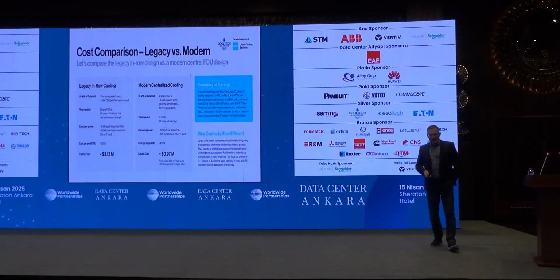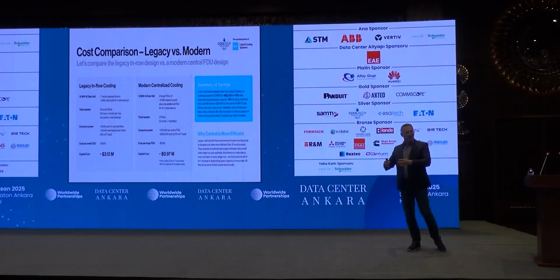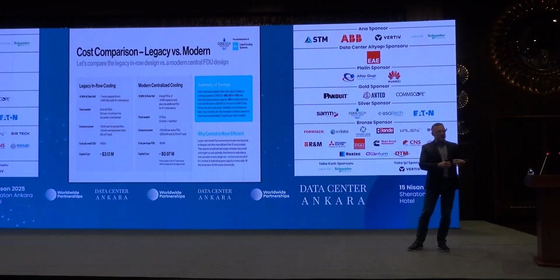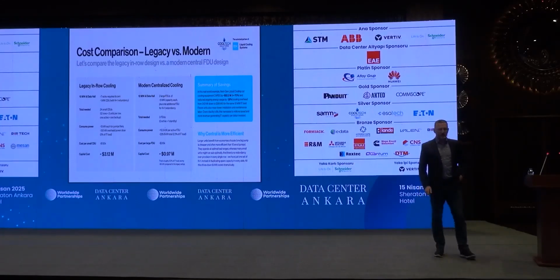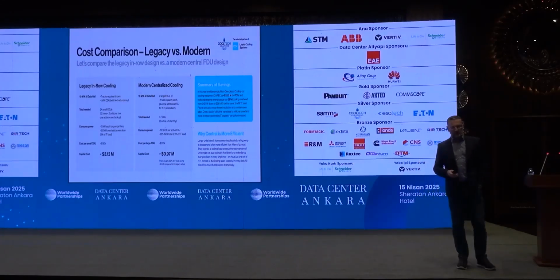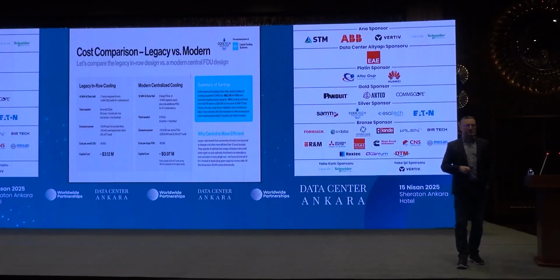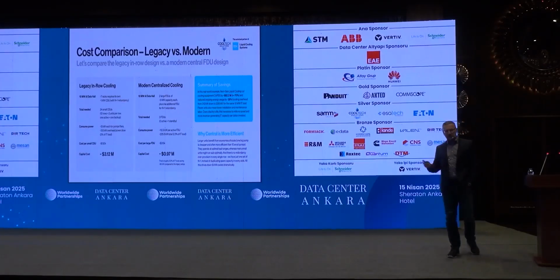That's important. If we compare those two types of building systems - lots of small CDUs in between the racks, in-row units, versus centralized CDUs which cover more racks - there's a huge cost difference. It also accounts for other items, like lead times. When you want to get those racks and manifolds and pipes and everything, it's important to make sure that you are energy efficient but also cost efficient. That's very, very important.